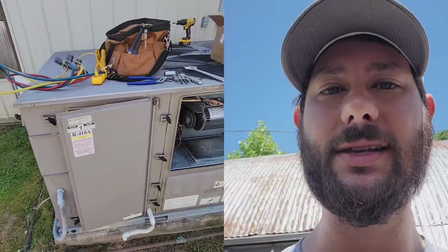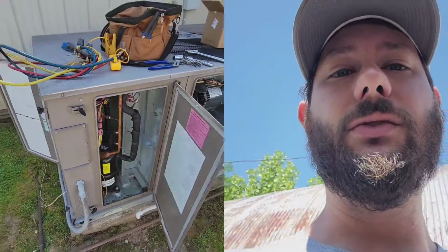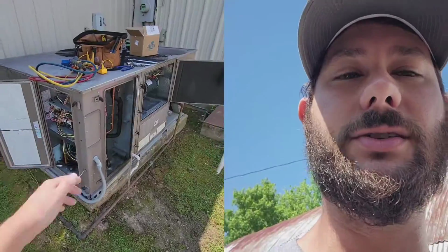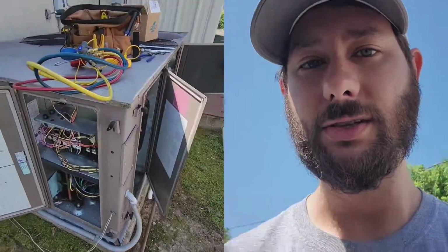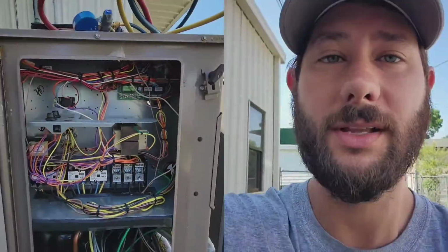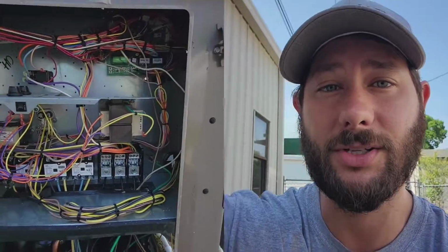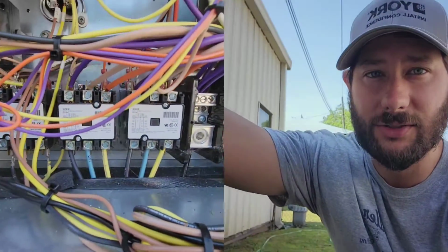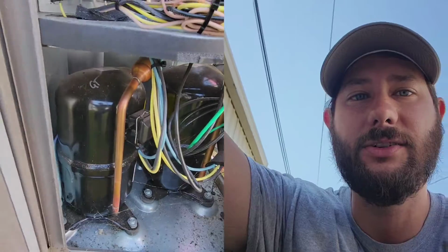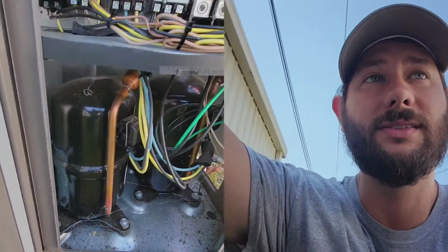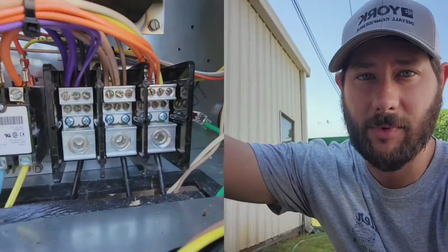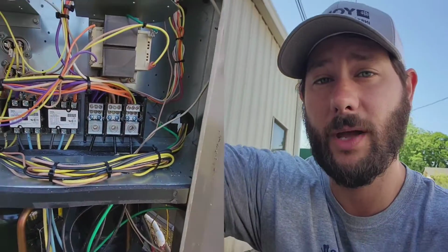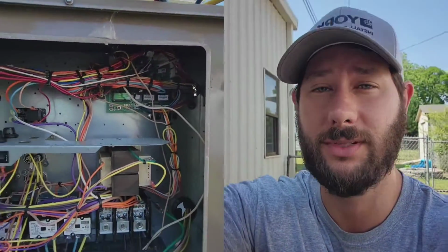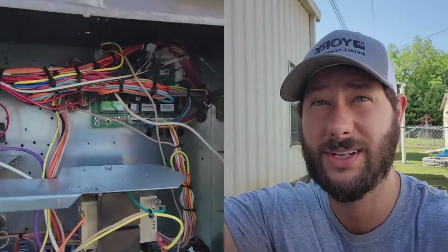So let's get started with today's episode by showing you all of the different sections, and then we'll go in depth. This right here is the electrical component section, and you've got a bunch of contactors here, and these contactors are for the compressors, because you've got two circuits on this system, and you've got your incoming power. It's three-phase, 208, 230. Make sure you know what you're dealing with, whether it's 208, 230, or 460 volt.